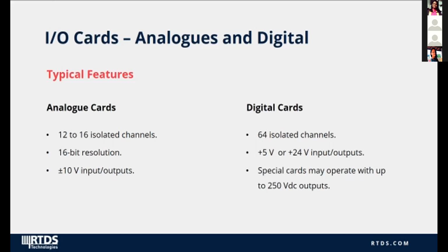Typically, digital I/O cards include 64 isolated channels, plus 5 or plus 24 volt inputs and outputs. A special card may operate with up to 250 volt DC output, especially for protection relay testing. Usually, I/O cards are modular and multiple cards can be simultaneously connected to the simulator to obtain hundreds of signals if required.